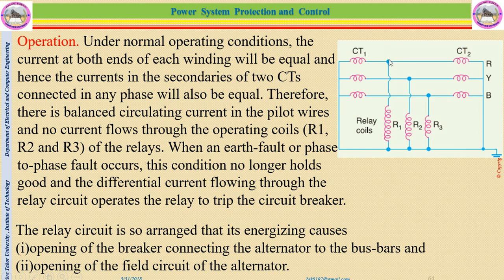If this one is equal to this one, there is no current which may pass through this relay coil R1. And if these are equal, there is no current which passes through R2, or relay 2. Therefore, there is balanced circulating current in the pilot wires, and no current flows through the operating coil, that means the corresponding relay coils R1, R2, R3 of the relay.